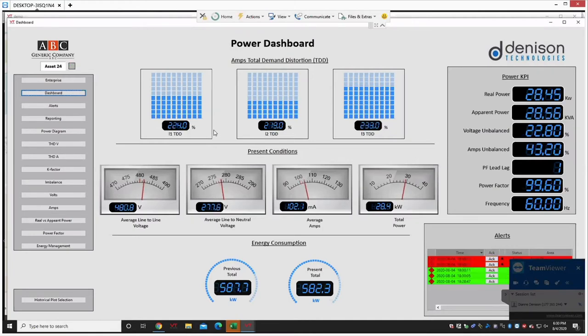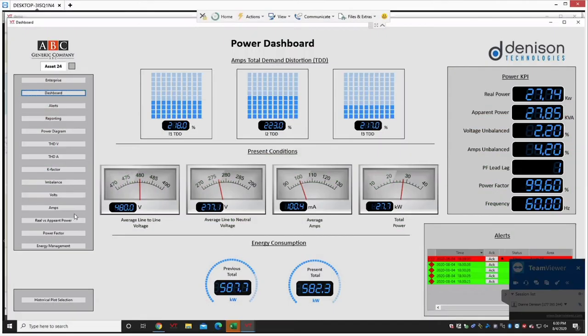Red alerts and yellow alarm conditions are triggered when events occur outside of industry spec ranges. For example, power measurements falling outside of relevant IEEE specifications will trigger alerts and alarms for attention and possible action. Alerts and alarms can be partitioned so that certain users receive notification based on type, severity, or frequency. For example, the maintenance engineer might want to receive notice of all alarms of a specific type, but the plant manager might only want to receive higher severity alarms or a daily report showing the roll-up of all alarms for that day. The left-hand toolbar allows users easy navigation to launch the next set of screens.